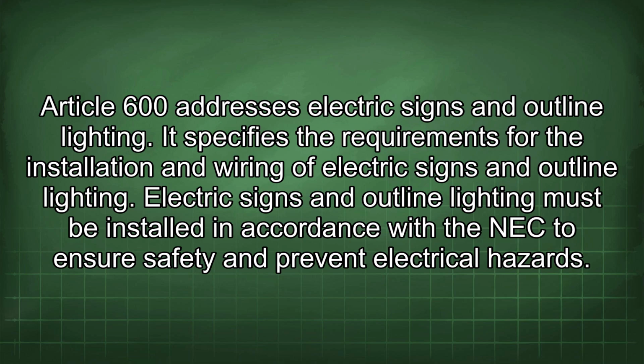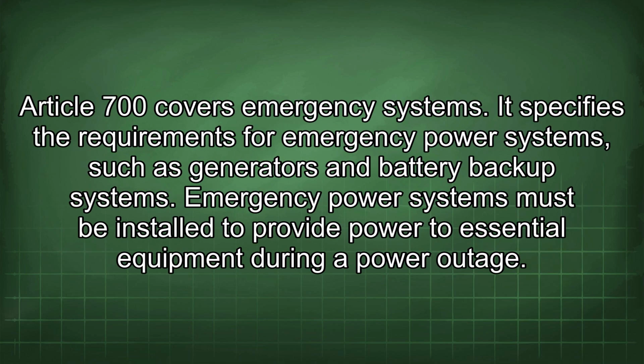Article 600 addresses electric signs and outline lighting. It specifies the requirements for the installation and wiring of electric signs and outline lighting. Electric signs and outline lighting must be installed in accordance with the NEC to ensure safety and prevent electrical hazards. Article 700 covers emergency systems. It specifies the requirements for emergency power systems such as generators and battery backup systems. Emergency power systems must be installed to provide power to essential equipment during a power outage.